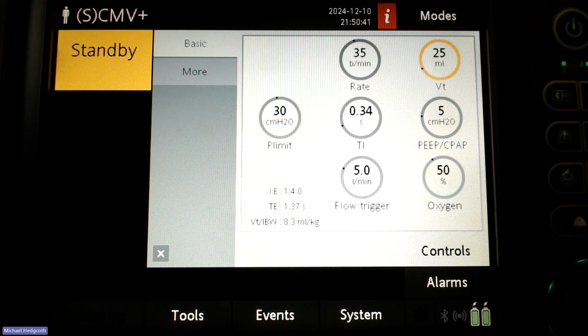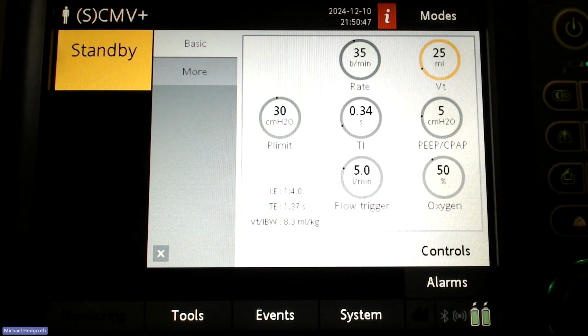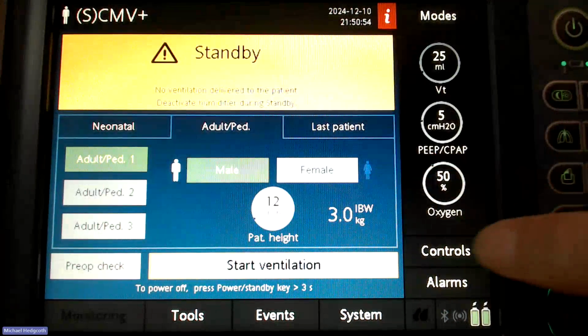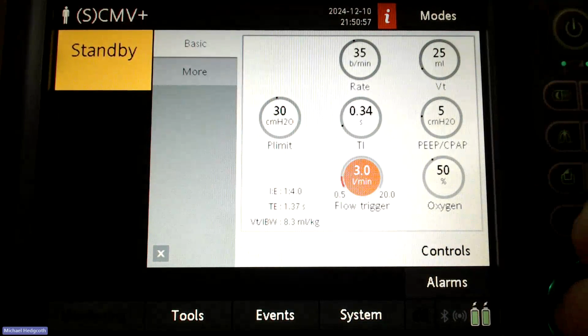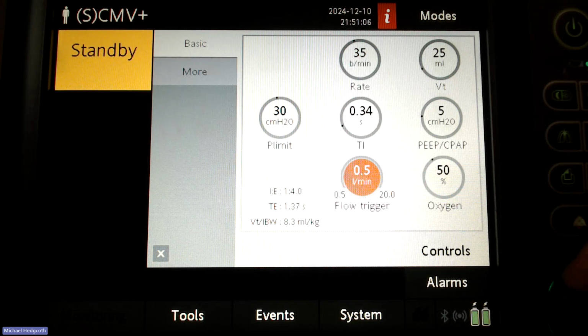That's all we're doing on here. And then we're going to go ahead and move forward with starting ventilation. The flow trigger, remember, starts at 5 liters per minute under the adult peds tab. That may need to be lower and will most likely need to be lower. So if we drop that down, we can move it as needed. If we see the patient struggling to trigger, we can keep going down. We could always go all the way down to 0.5 liters per minute. If we're seeing auto triggering, we can always move it up a little bit. So starting at lower than 5 is probably going to be necessary. Where that exactly falls is going to be very patient dependent, but you do have a good range to work with, making sure that they aren't working too hard to trigger the ventilator.